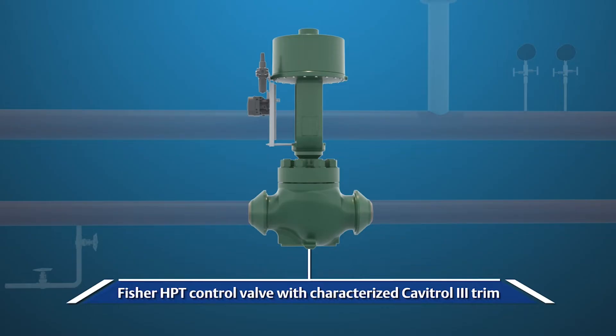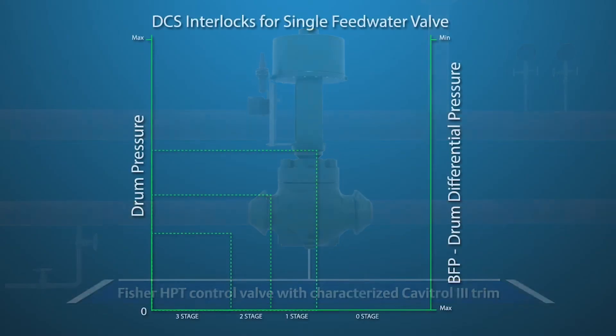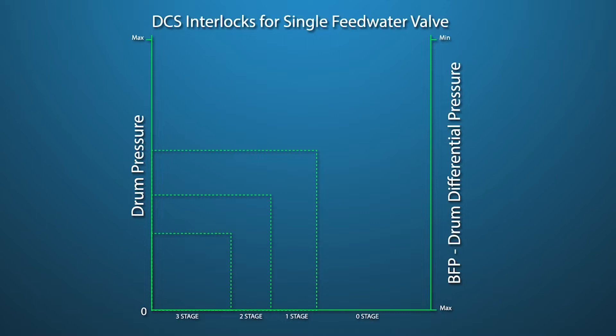If a single valve is used, the DP between the pump discharge and drum needs to be monitored by the control system. An interlock in the control system should be established to prevent the valve from opening past the anti-cavitation portion of the trim, until a non-cavitating DP is reached in the system.